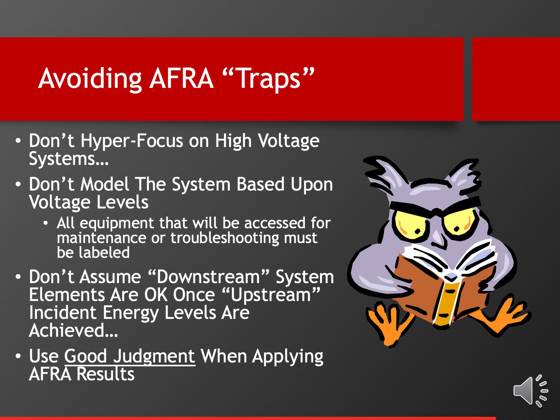Don't assume downstream devices are okay once upstream incident energies are okay. For example, it's possible on a 480 volt to 208 transformer that on the 480 volt side it may be 6 or 7 calories, and on the 208 system, because of the overcurrent devices, it may be 27 calories or something like that. So don't just stop at a system when you think it's okay on a higher voltage system, because again, do the calculations, make sure what you've got downstream, and stop managing the process when the calories get below a set amount. And I would recommend 10 calories myself.